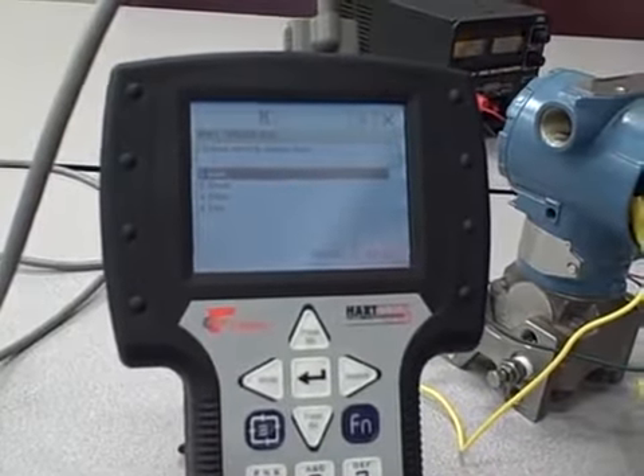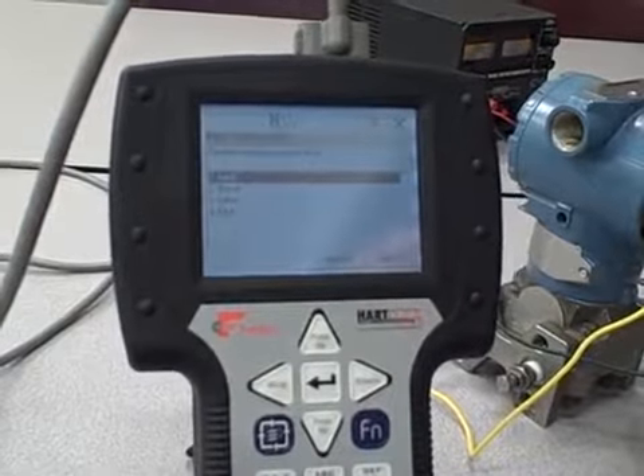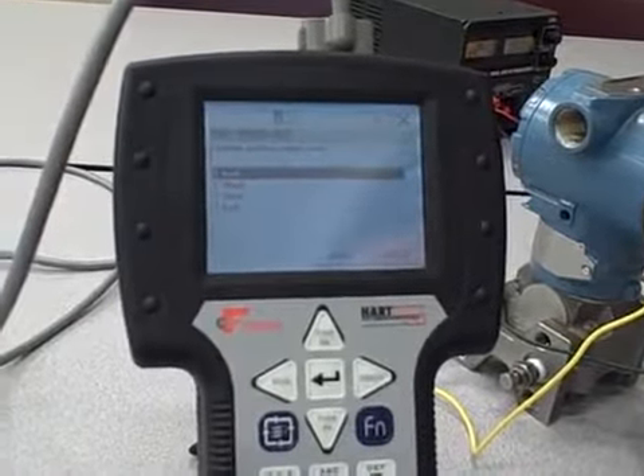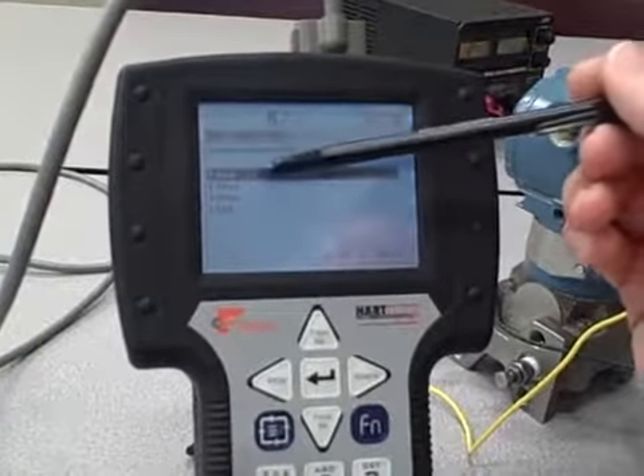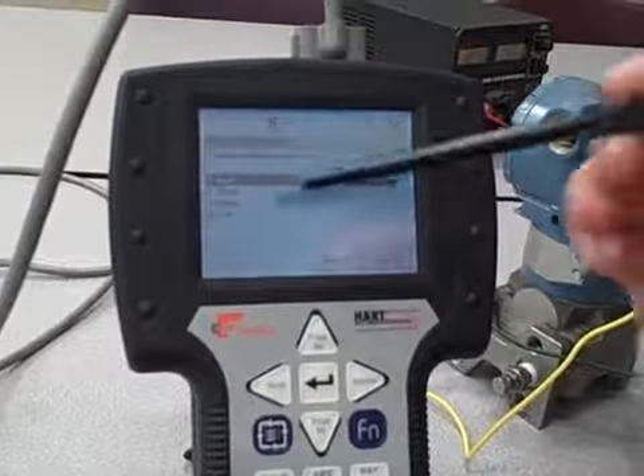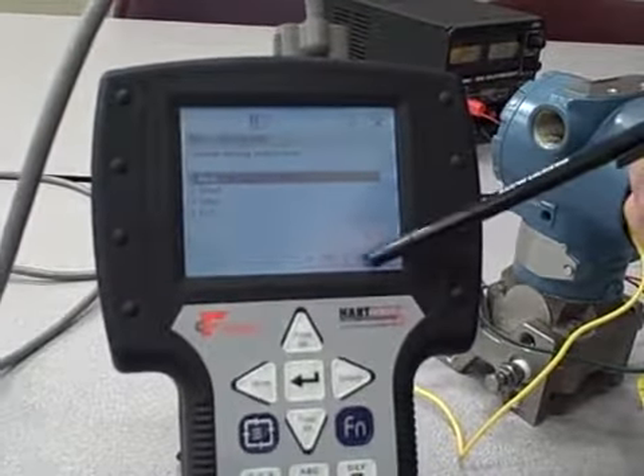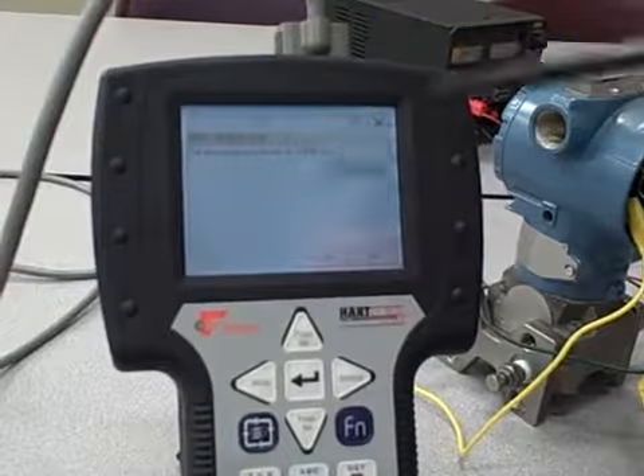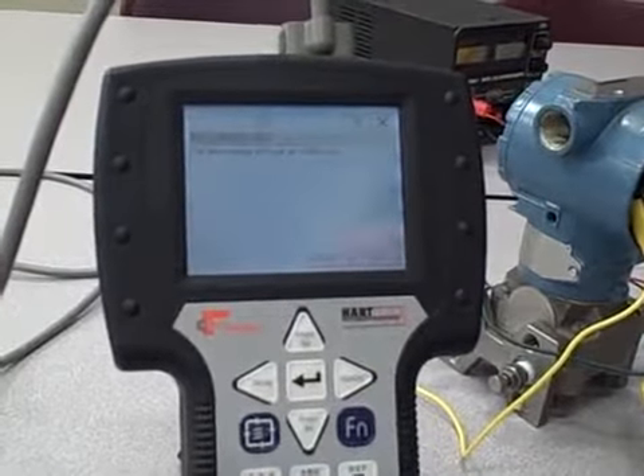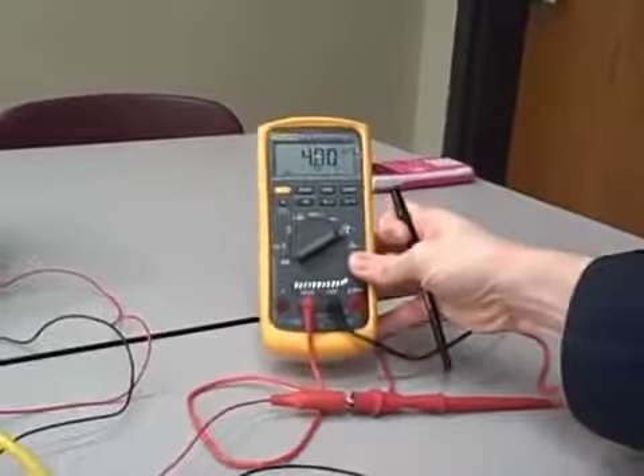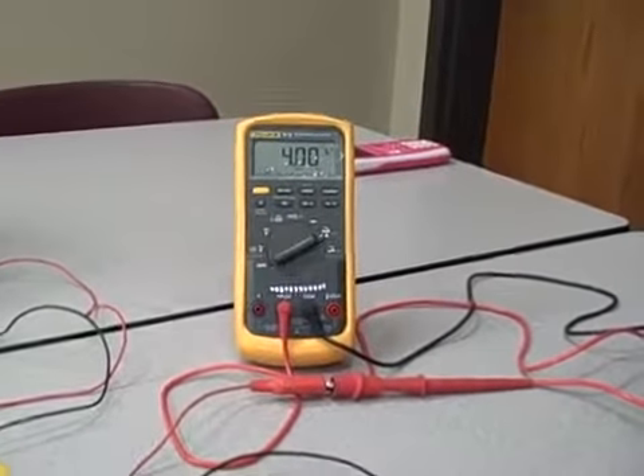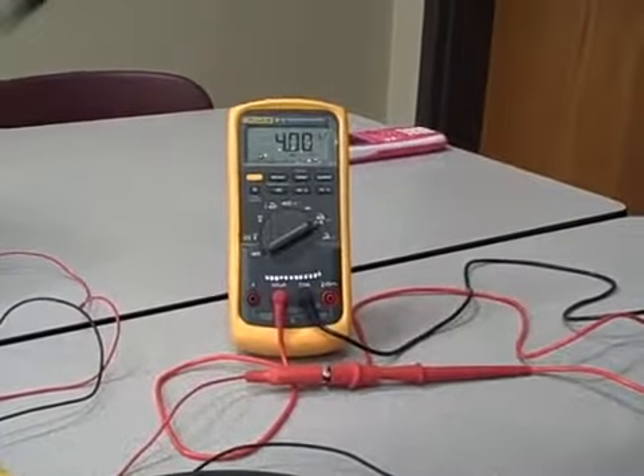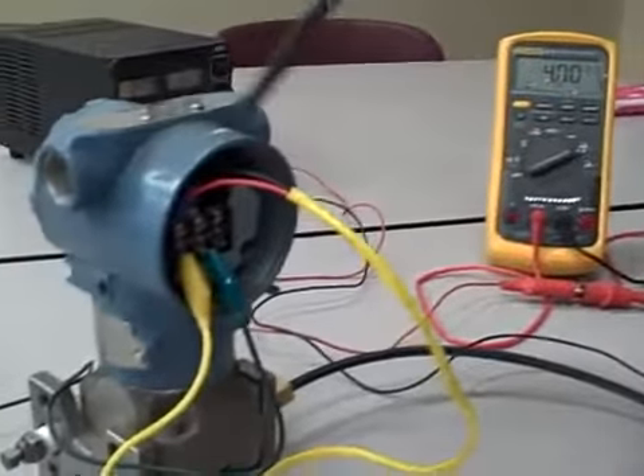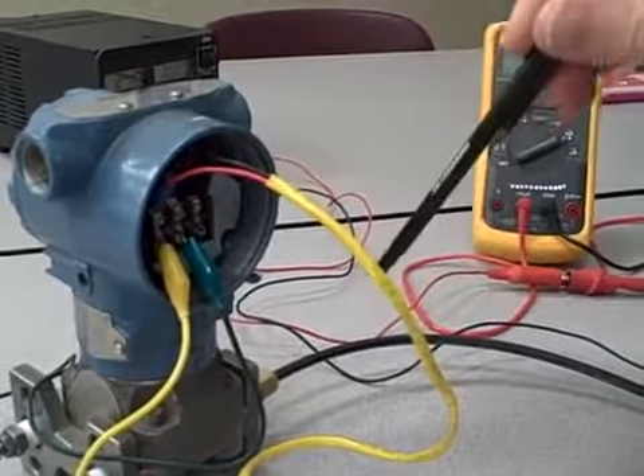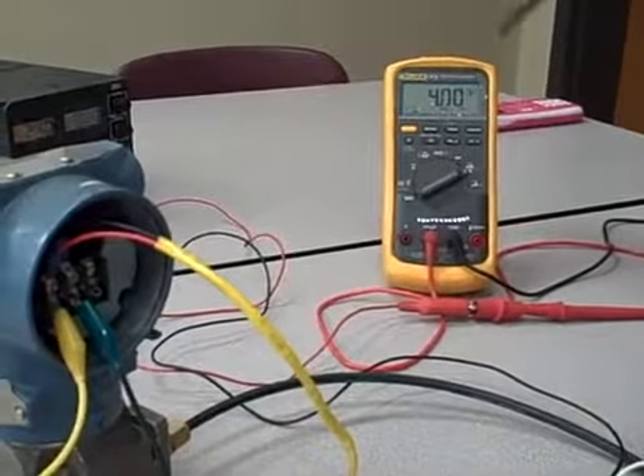If you want to see if there's some sort of a wiring problem or calibration problem on a device, what you can do is tell the transmitter to go directly to either 4 milliamps exactly, 20 milliamps exactly, or some other value. For example, I'll tell it to go to 4 milliamps. It says here, field device output is fixed at 4 milliamps. If we look at our loop current meter, we see that the current is now fixed at 4 milliamps. This is despite the fact we still have about 500 inches of water column pressure applied to the transmitter. It is now ignoring that applied pressure and fixing the output at 4 milliamps.